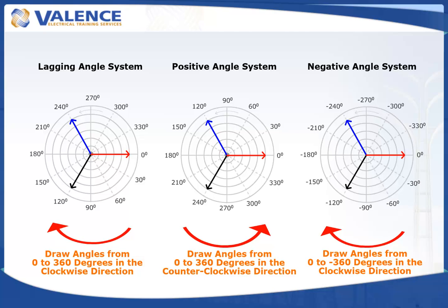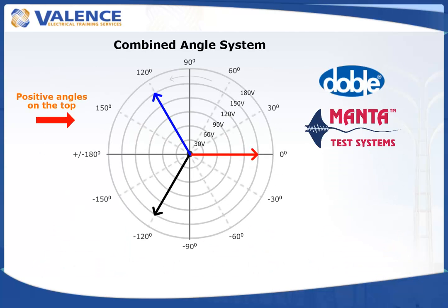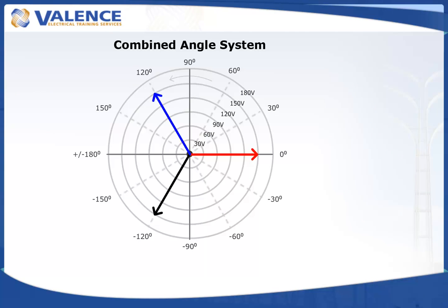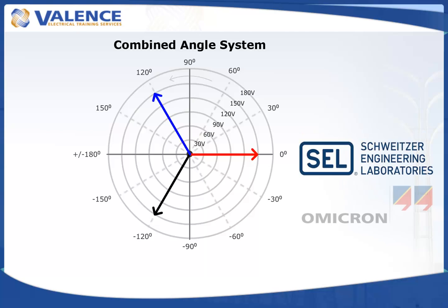There is a fourth angle system that combines the positive system from DOBLE and MANTA test sets from 0 to 180 degrees on the top half of the phasor diagram and the negative system from GE UR relays on the bottom half. This combined angle system is probably the most popular system in the world because it simplifies any math equation that uses angles. It is possible, or even likely, to get results greater than 360 degrees when using the other angle systems, which means you always have to be watching for it and modify your answers accordingly. This rarely happens with a combined angle system, which is used in SEL relays and Omicron test sets.